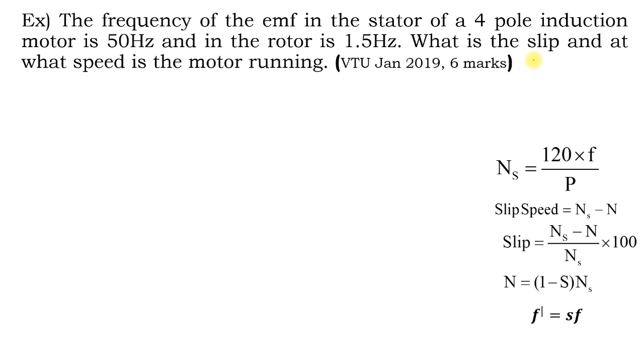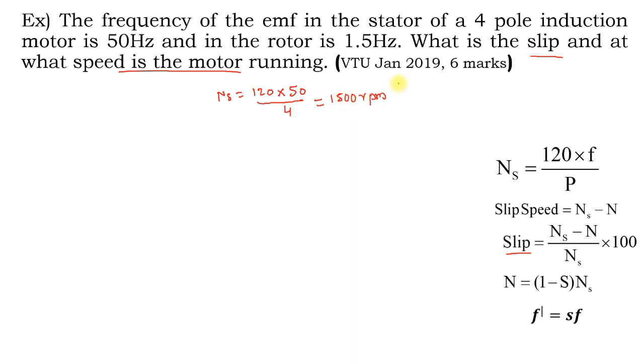In this problem they are asking us to find the slip and speed of the induction motor. To find the slip, ns is required. ns = 120 × f / P = 120 × 50 / 4 = 1500 rpm.